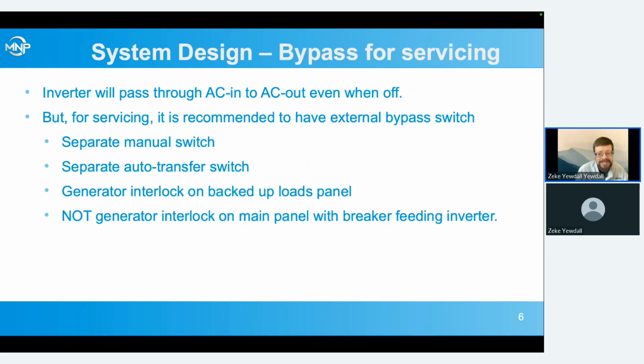One thing we want to think about is, even though our inverter has an internal transfer switch, it's still recommended that we have an external bypass switch, just in case we're servicing the system, we're doing work on it, maybe we've got to swap a battery out, whatever, so that you still can get grid power through to your backed up loads. That could be a separate manual transfer switch, just an on-off knife type blade type switch. That could be an auto transfer switch, kind of set up in the opposite direction as we were just talking about, where it normally feeds inverter power through to your backed up loads and automatically switches to the grid power if for some reason it loses inverter power.